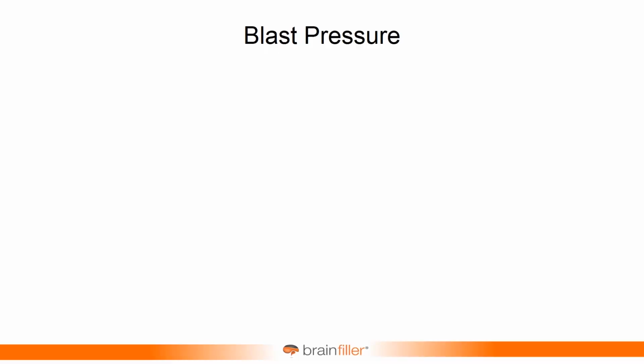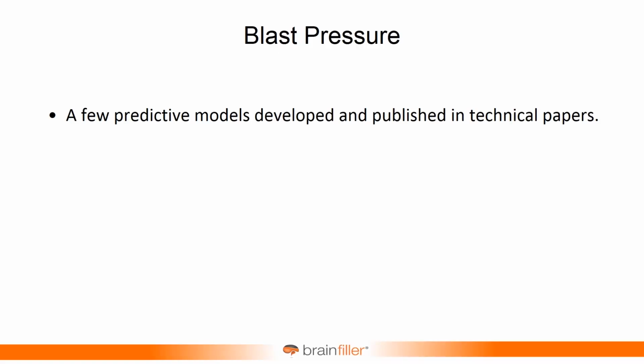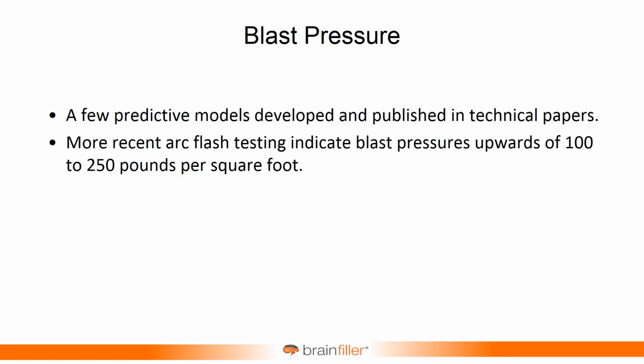This really won't be rolled into the 1584 standard, but it was some really good test data that we ended up with. And then also blast pressure. Blast pressure is still something that we're scratching our heads about. The thought is, yes, if there's a really significant arc flash, and it's really more short circuit dependent, you can have a pretty significant blast pressure. But the measurements are showing that the pressure is somewhere between 100 and 250 pounds a square foot. I mean, it's significant, absolutely. It can knock you off a ladder, off a scaffold, do all kinds of things like that.